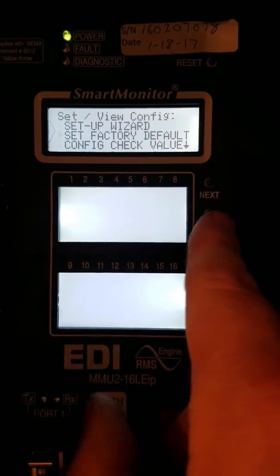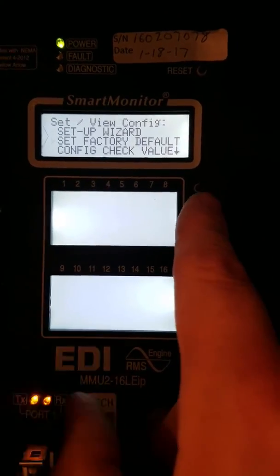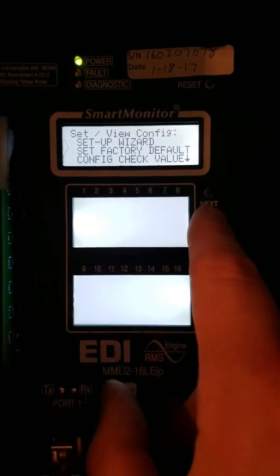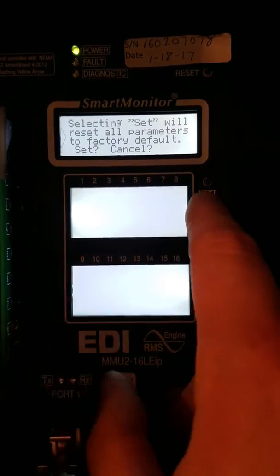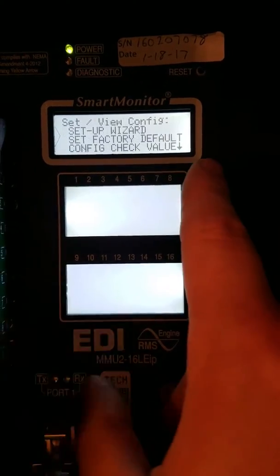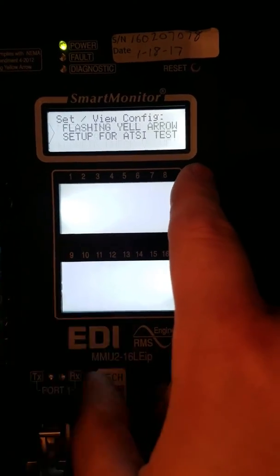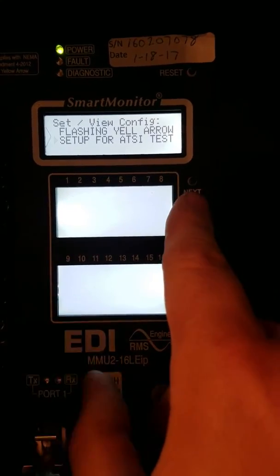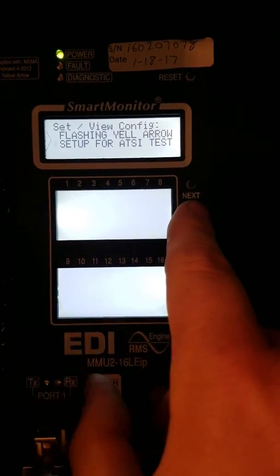We're going to assume this was tested as a full-fledged flashing yellow arrow, or we don't know what's in here. So we're going to set factory default. I always do this to wipe out the flashing yellow arrow parameters that may have been programmed in there.